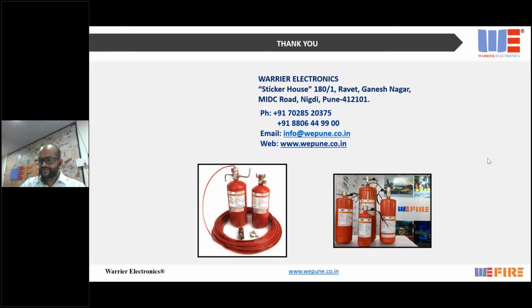In any case, sprinkler and fire hydrant systems are not meant to suppress the fire. They're only meant so that if there's a fire in a particular room, the sprinkler ensures it does not spread to adjacent rooms. That is the purpose of a sprinkler; it will not suppress the fire. Moreover, sprinklers are water-based, so they can destroy electronic equipment, whereas what we use is gas-based, non-conducting equipment. So it is absolutely safe for electronics, for documents, and safe for human beings to be used in occupied spaces. These are basically equipment-level protection, so I would not recommend replacing your existing system, only adding on to it.